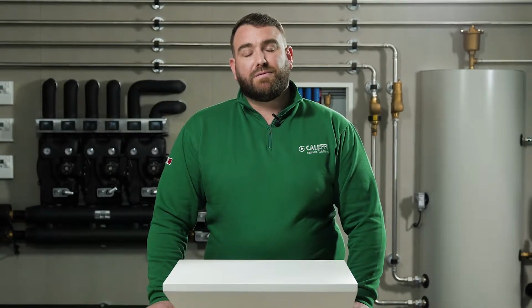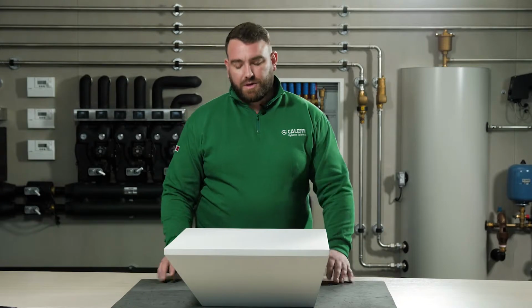This includes flushing through the horizontal mains, flushing through the mains floor by floor, flushing through the entire system, and a two-stage flush through the terminal unit, including forward flush and backward flush to drain. Steps 1, 2 and 3 are carried out using the bypass unit. Step 4 is carried out flushing to drain. To enable us to achieve the correct outcome, we must use the following components.